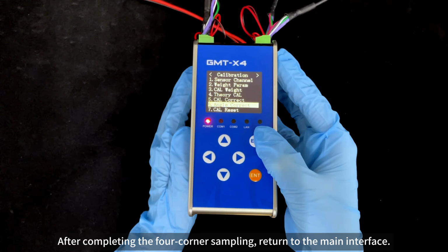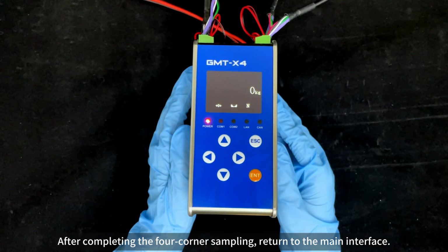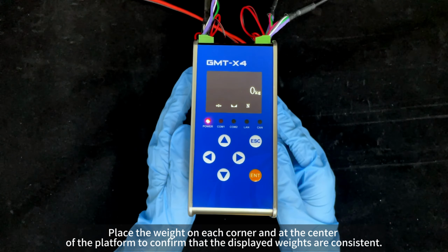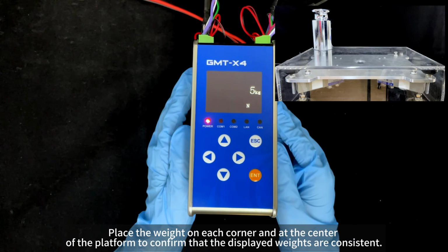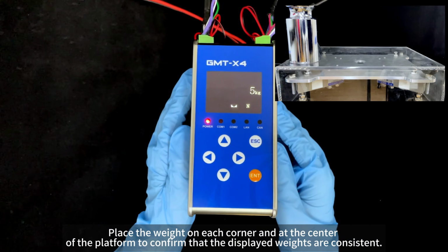After completing the 4-corner sampling, return to the main interface. Place the weight on each corner and at the center of the platform to confirm that the displayed weights are consistent.